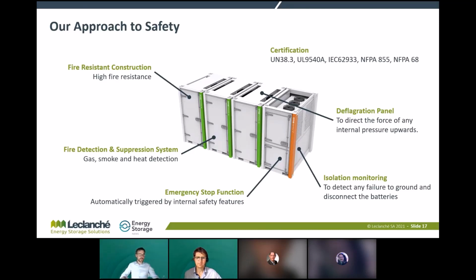Over the entire battery system, from the combiner block up to the battery blocks, we have an emergency stop function, triggered by anomalies detected by the EMS, or by an emergency button used by first responders or operators, or by devices like ground fault detection. We also have isolation monitoring equipped in the combiner block, and a deflagration panel on each battery block, which directs any overpressure upwards to improve human safety on site.